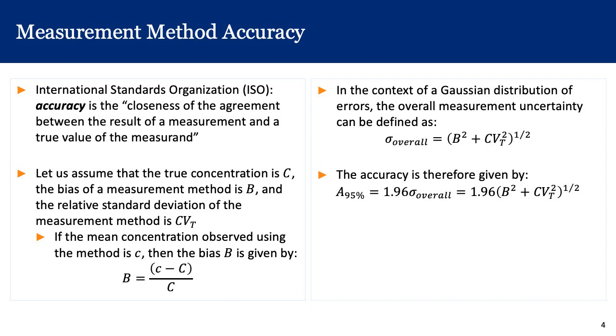Another way to describe measurements is using measurement method accuracy. The International Standards Organization, ISO, defines accuracy as the closeness of the agreement between the result of a measurement and the true value of the measurement. Assume the true value of the concentration is C, the bias in the measurement method is B, and the relative standard deviation is the total coefficient of variation Cv_t.